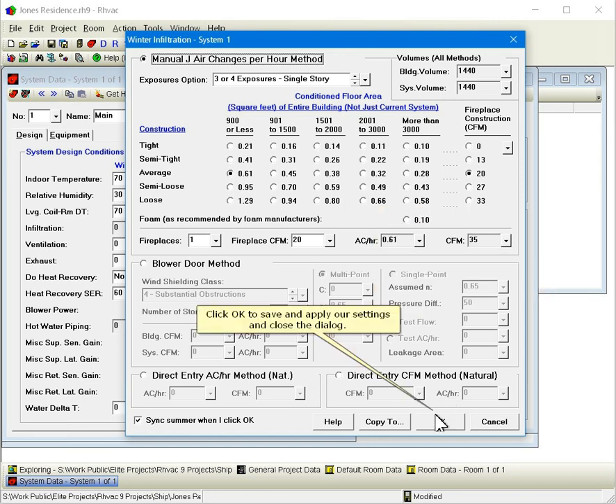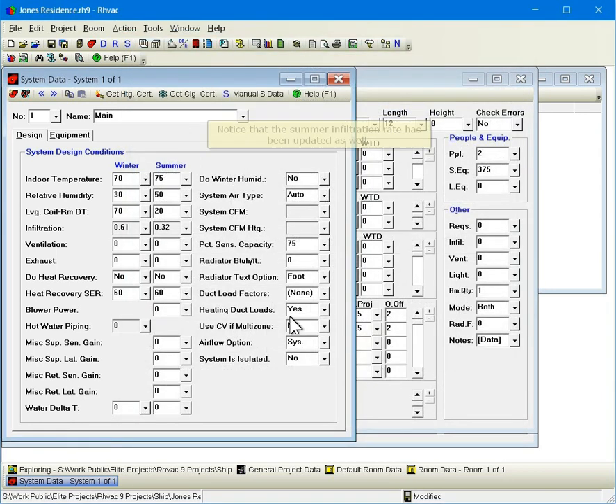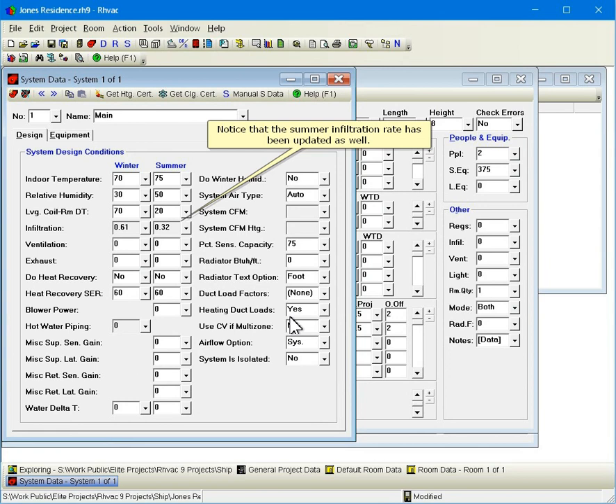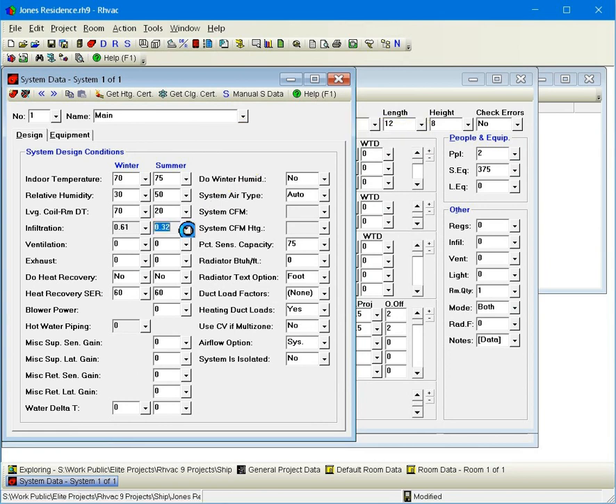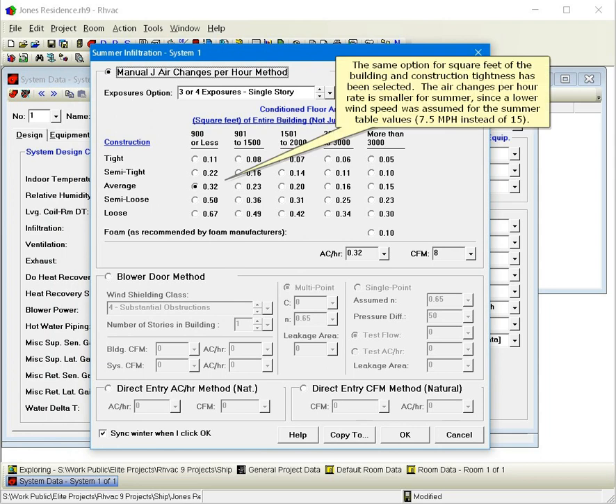Click OK to save and apply our settings and close the dialog. Notice that the summer infiltration rate has been updated as well. The same option for square feet of the building and construction tightness has been selected. The air changes per hour rate is smaller for summer, since a lower wind speed was assumed for the summer table values, 7.5 miles per hour instead of 15.